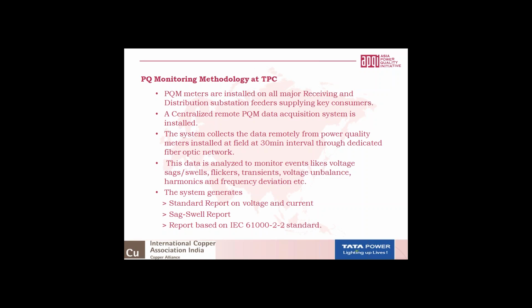So we installed a centralized remote power quality meter data acquisition system in the Tata Power Company. This system collects the data remotely from power quality meters installed in the field at every 30-minute interval, and we are using our dedicated fiber optic network for this particular activity. This is a very reliable method of collecting data, and usually we do not experience any problem with this methodology. This data is analyzed further, and events like voltage sags and swells, flickers, transients, unbalance in voltages, harmonics, frequency deviation, etc., we are checking by just collecting the event data and analyzing it.